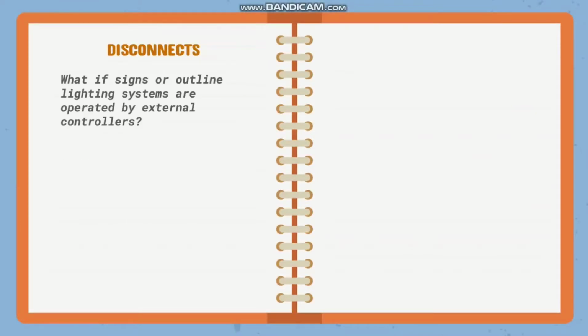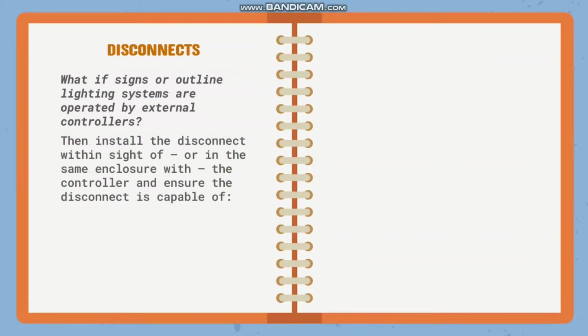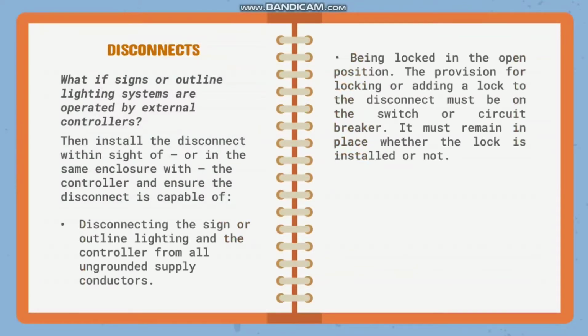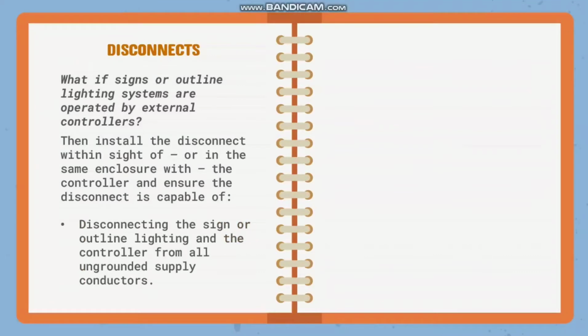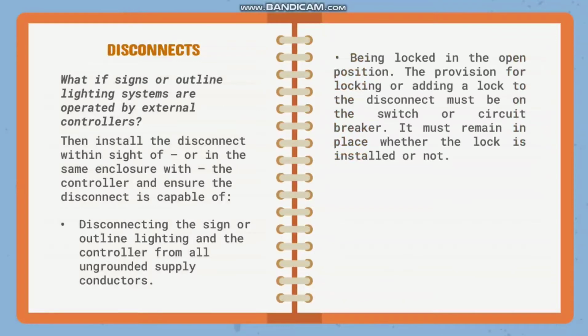So, what if signs or outline lighting systems are operated by external controllers? The answer is, install the disconnect within sight of or in the same enclosure with the controller and ensure the disconnect is capable of, first, disconnecting the sign or outline lighting and the controller from all ungrounded supply conductors. And being locked in the open position, the provision for locking or adding a lock to this disconnect must be on the switch or circuit breaker. It must remain in place whether the lock is installed or not.